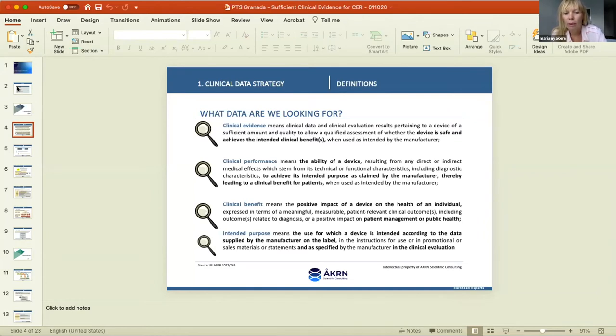And then finally, the intended purpose, which is like the holy grail in medical devices. It's the use for which the device is intended according to the data supplied by the manufacturer on the label. It's also provided in the instructions for use and any promotional material, and it's specified by the manufacturer and then used in the clinical evaluation. So the intended purpose is really why you designed your product, why you probably early on thought there was an unmet medical need and decided to solve that need, but that has to translate into regulatory terminology, packaged into an intended purpose.